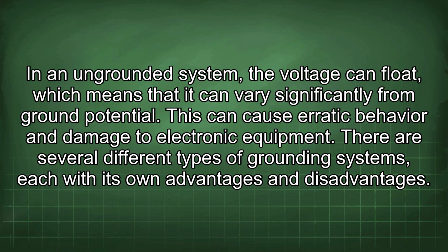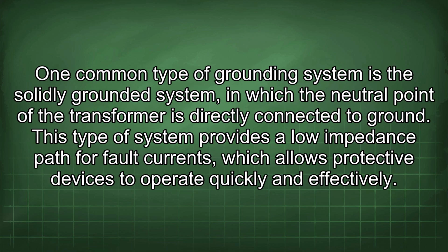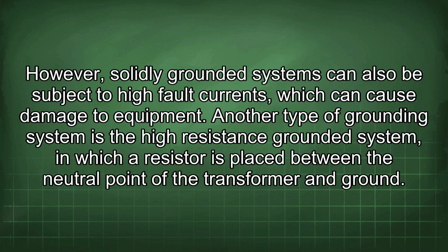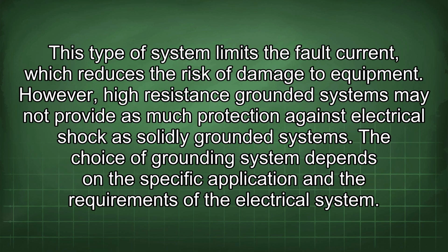There are several different types of grounding systems, each with its own advantages and disadvantages. One common type of grounding system is the solidly grounded system, in which the neutral point of the transformer is directly connected to ground. This type of system provides a low impedance path for fault currents, which allows protective devices to operate quickly and effectively. However, solidly grounded systems can also be subject to high fault currents, which can cause damage to equipment. Another type of grounding system is the high-resistance grounded system, in which a resistor is placed between the neutral point of the transformer and ground. This type of system limits the fault current, which reduces the risk of damage to equipment.